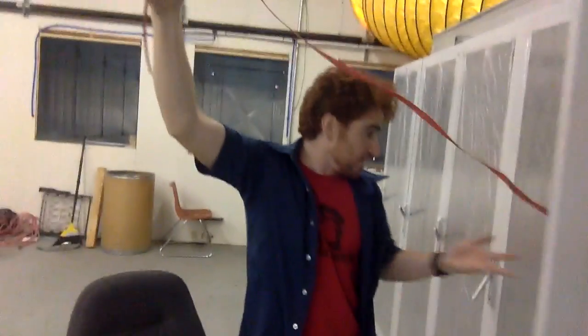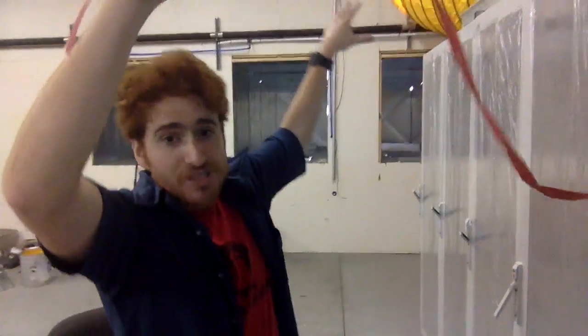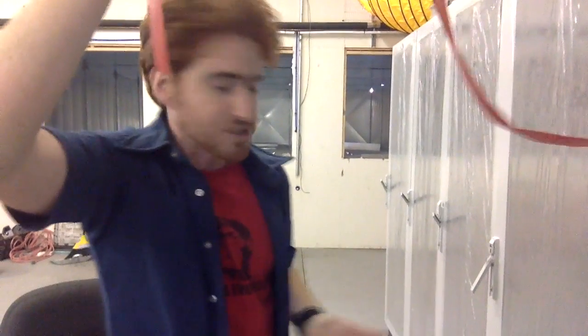The airflow that we're pulling through our machine, our racks, is quite considerable. And this is airflow that adds to the fans on the machines themselves. We have huge exhaust fans that force extra air and extra cooling capacity through our machines. They perform better stacked like this in a very dense configuration than they would if they were just in an empty room all by themselves. Now let's head over to our containment aisle itself. And I apologize, it's going to get a little bit noisy in here.